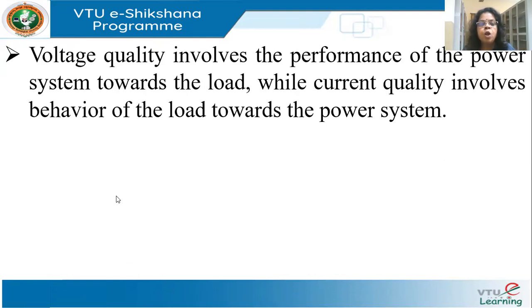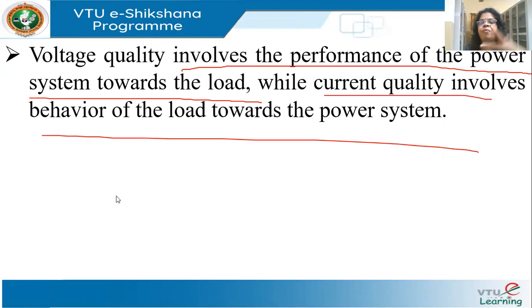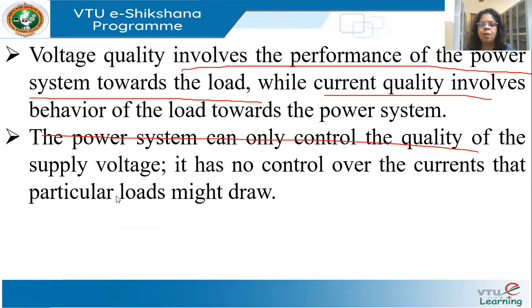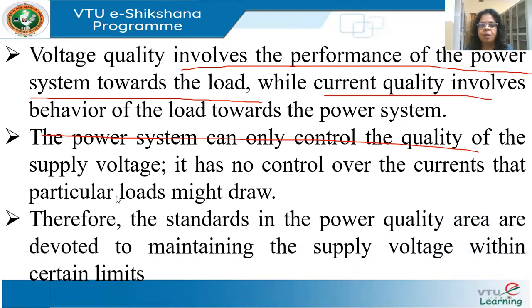Voltage quality involves the performance of the power system towards the load, how the system affects the load, and current quality involves how the load affects the system. The type of current drawn will affect the drops in the system. So voltage quality is determined by the utility most often, and current quality is determined by the load. The power system can only control the quality of the supply voltage, and has no control over the current. Therefore, the standards in the power quality area are devoted to maintaining the supply voltage within certain limits.